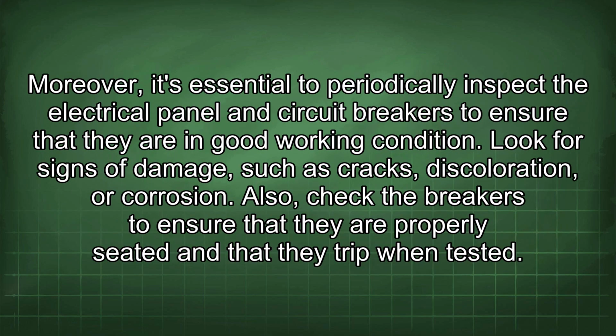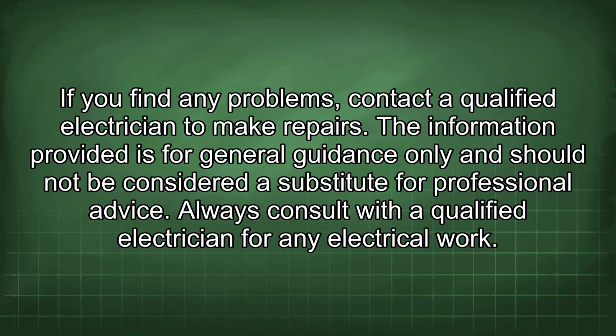Moreover, it's essential to periodically inspect the electrical panel and circuit breakers to ensure that they are in good working condition. Look for signs of damage such as cracks, discoloration, or corrosion. Also, check the breakers to ensure that they are properly seated and that they trip when tested. If you find any problems, contact a qualified electrician to make repairs.